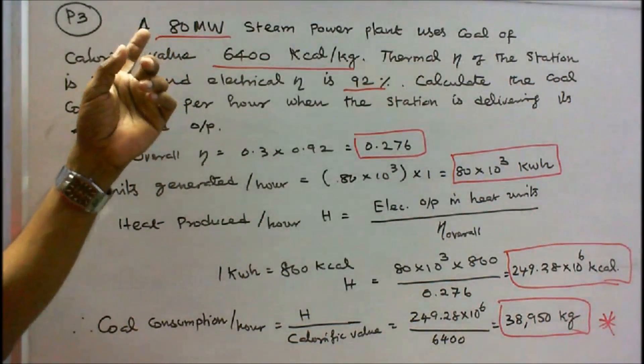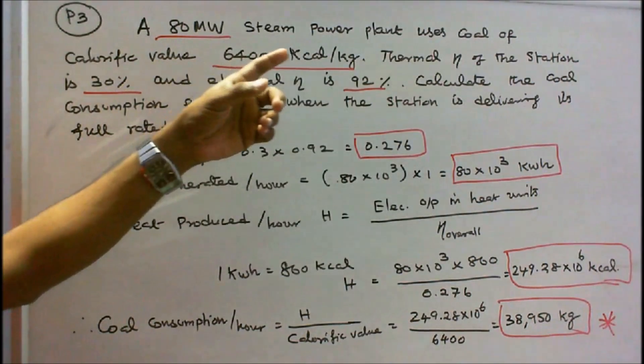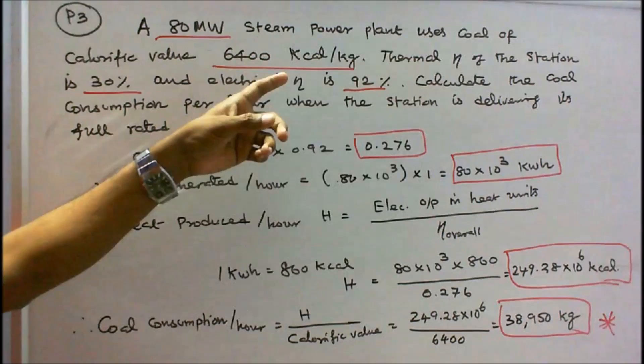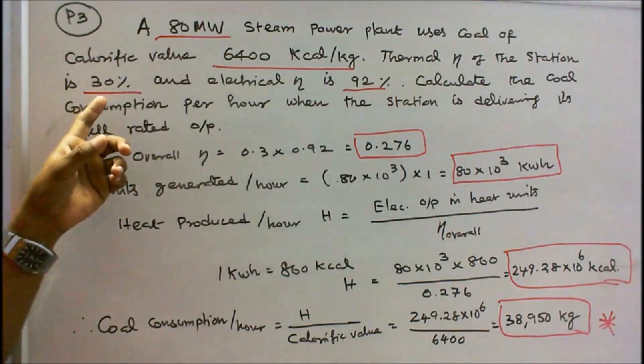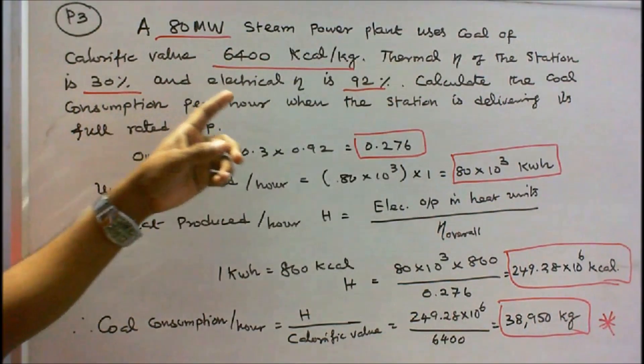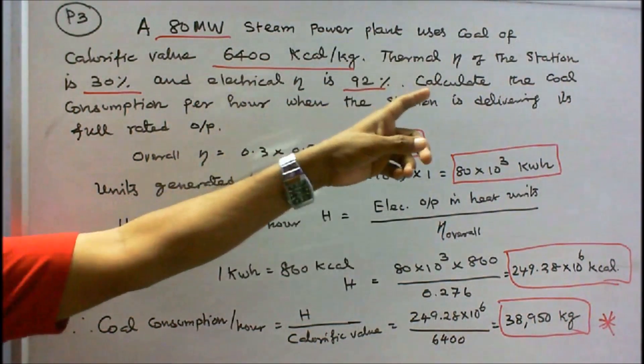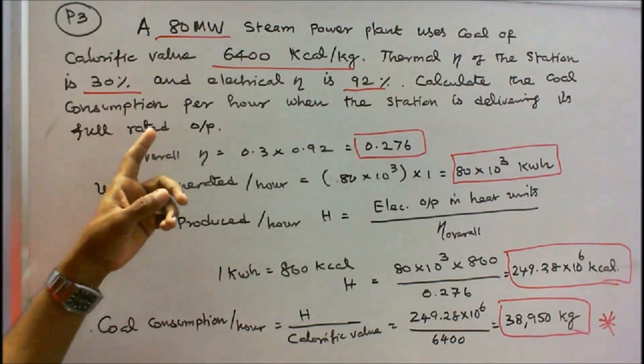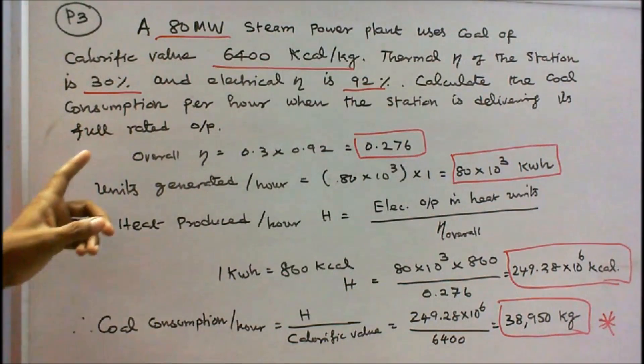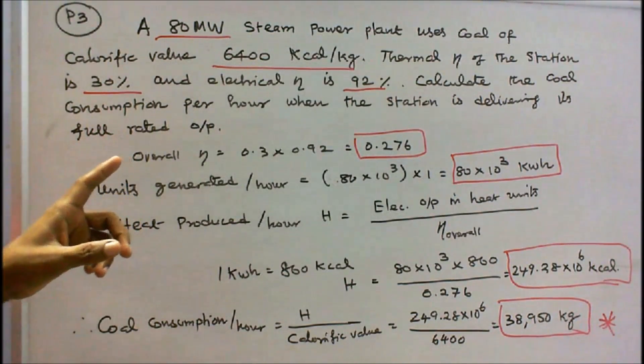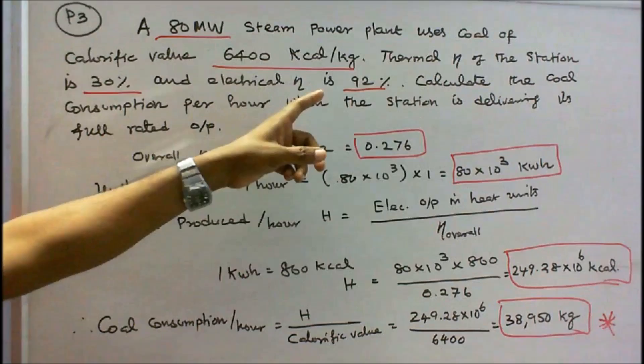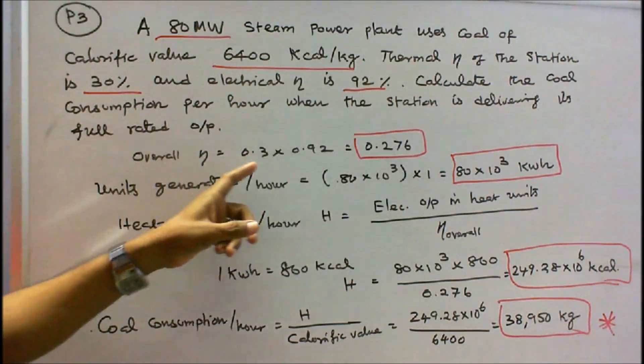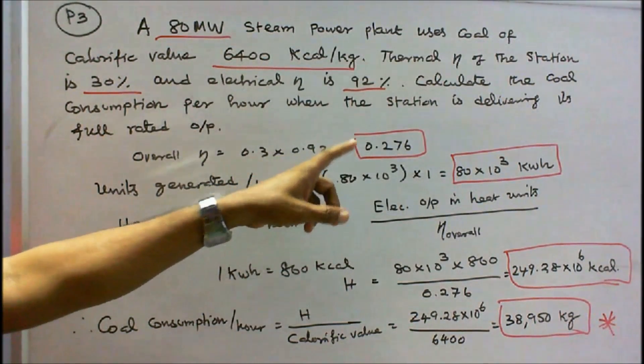Problem 3: an 80 megawatt steam power plant uses coal of calorific value 6400 kilocalories per kg. Thermal efficiency of the station is 30% and electrical efficiency is 92%. Calculate the coal consumption per hour when the station is delivering its full rated output. First step: overall efficiency = thermal efficiency × electrical efficiency = 0.3 × 0.92 = 0.276.